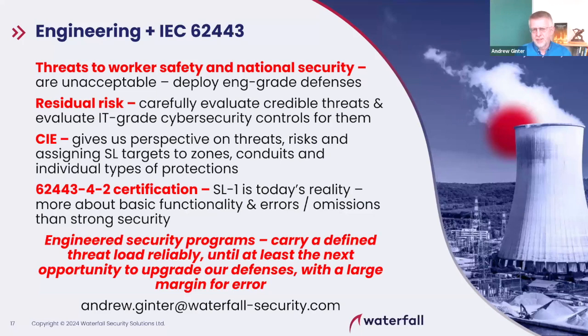Those air gaps disappeared 30 years ago. This is ancient history we're talking about in most sites. Most sites that think they still have an air gap today, when you do an audit of connectivity, they find dozens of connections to the outside world. Why is that? Well, partly it's just history. We didn't pay attention to the connections the vendors were sticking into these systems. We forgot the connections we stuck in there ourselves. Part of it is terminology.